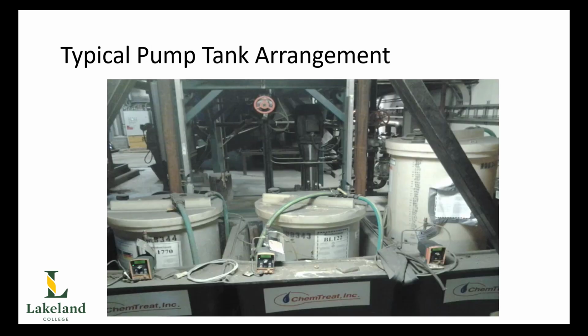Okay, so here's a typical pump tank arrangement, and this particular arrangement is a continuous feed system using pump tanks. In other words, our 3 plastic totes here, and again these totes are just the standard ones, sulfate, phosphate and amine. These are all filled up by those green hoses you can see attached to the top of the totes, and that's what the chemical rep would attach to fill up your chemical totes.